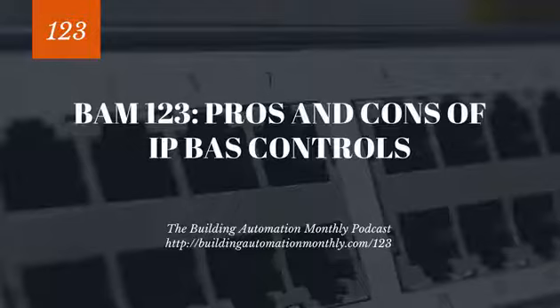Now, the reality is nowadays IP controls are pretty cheap, relatively speaking. Cost of Cat 5e, Cat 6 is relatively inexpensive. And with some of the topologies, which is a fancy way of saying physical layouts, that we're going to talk through in this episode, you'll see that it can actually not be as expensive as it used to be from an installation and a supporting perspective. So IP controls are essentially the same thing we've been doing with supervisory devices. All that's happened is that we have essentially taken the protocols that were used at the supervisory layer and we've pushed them down to the field layer.